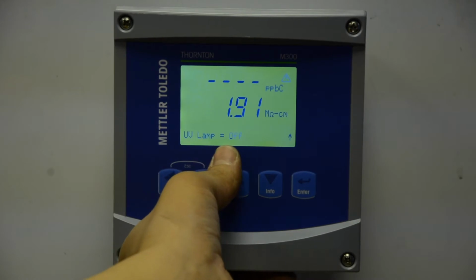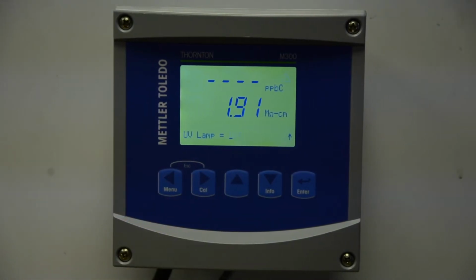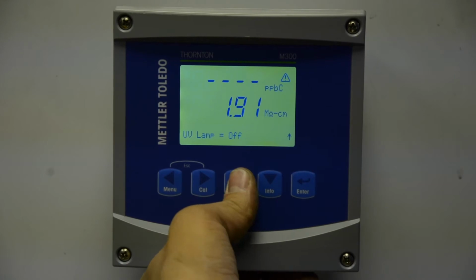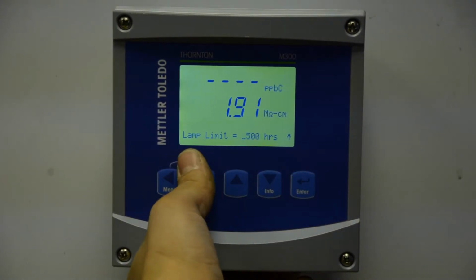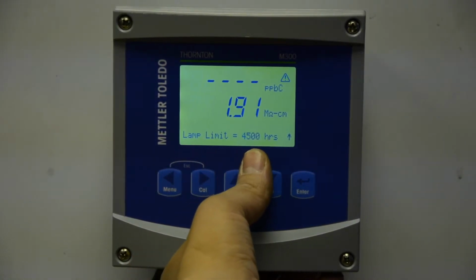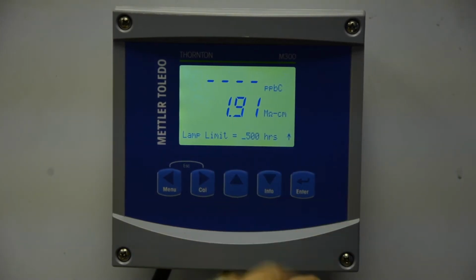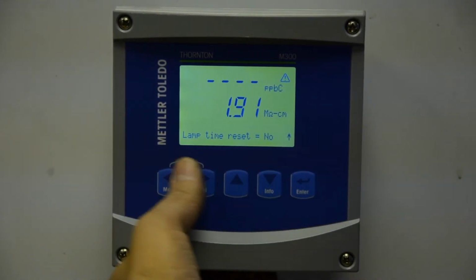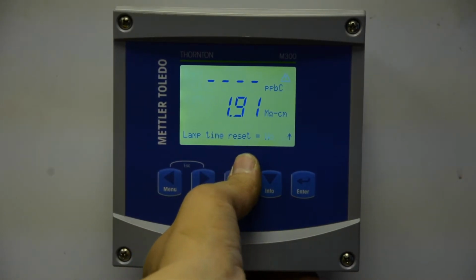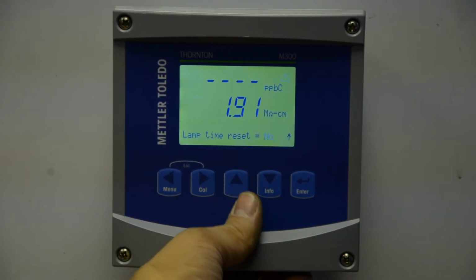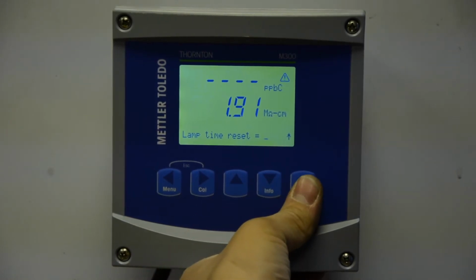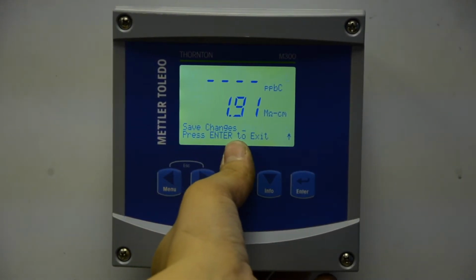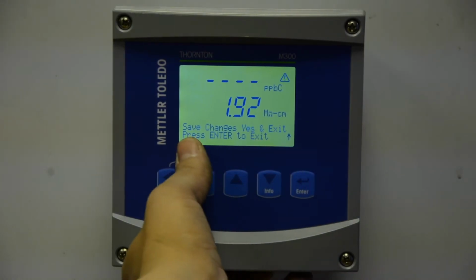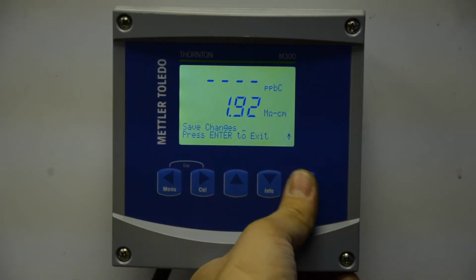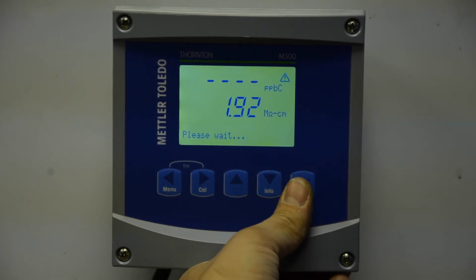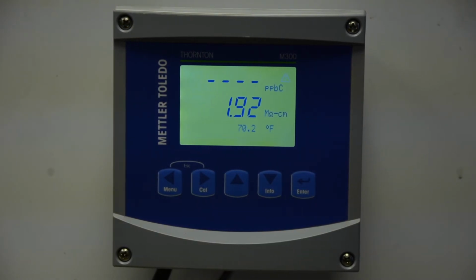They'll ask you for your UV lamp off. Right now the UV lamp is off because we have been working on the unit. So we're going to turn the lamp on, hit Enter, and then it asks you for the amount of hours. It should be 4,500 hours for this unit. So we're going to hit Enter, and then it asks you for lamp time reset. That's to reset those total hours to 4,500 hours. We want to scroll up to Yes and hit Enter. It says Save Changes, press Yes and exit. Press Enter to exit. So we're going to hit Enter, and now it's going to reset the hours for us.